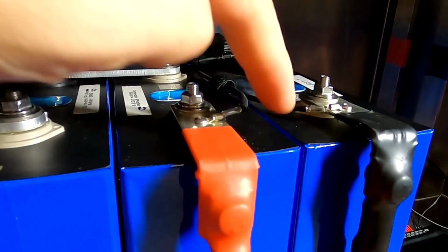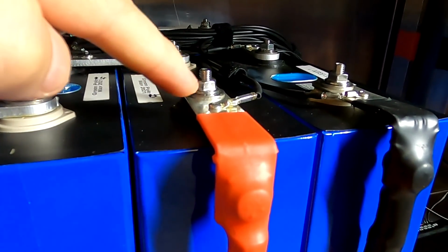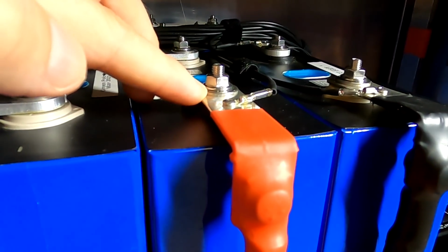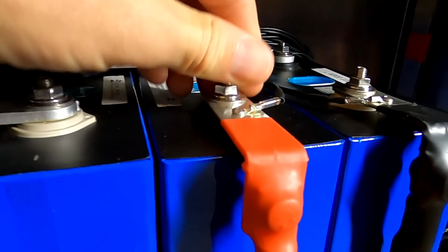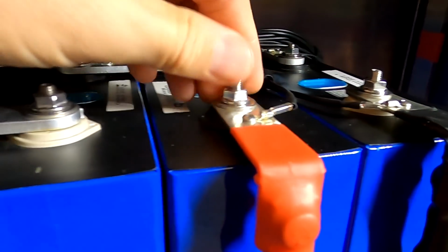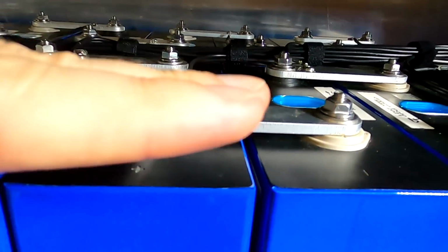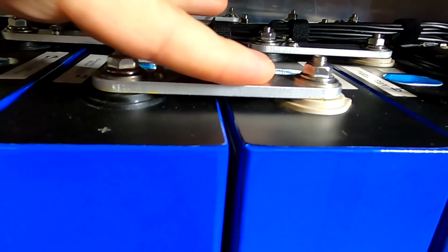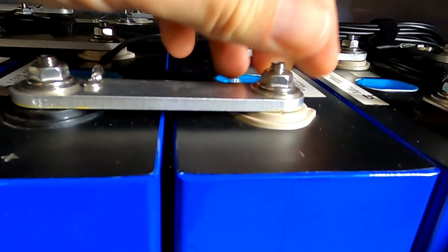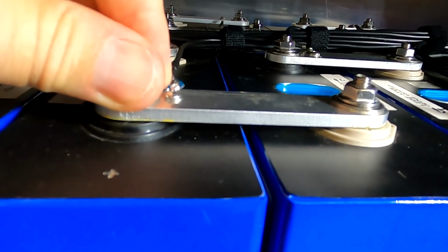So if these cells are on a different height, it doesn't matter, because the bus bar sits flat on the terminal. And of course then there's the best connection and no heat building up, while this one here could be a bit on an angle, and that's why it's heating up, why the terminals are getting hot, and eventually the bus bar as well.